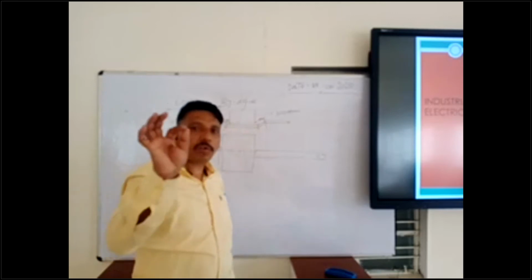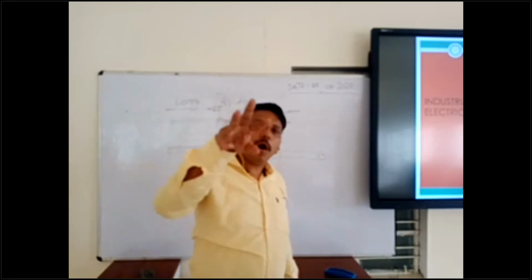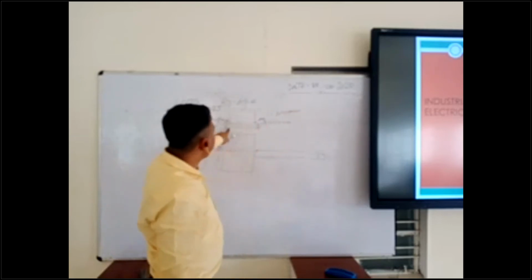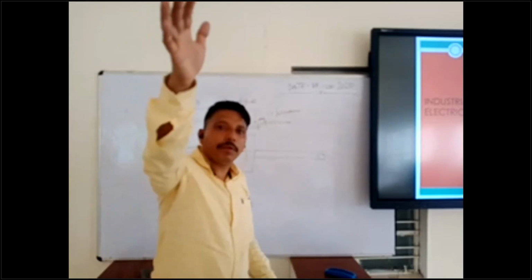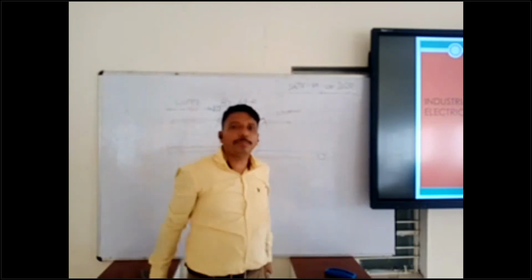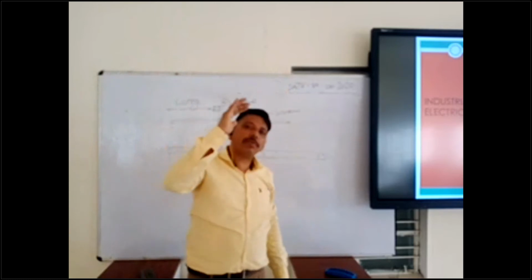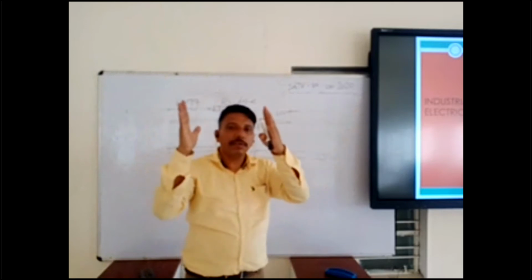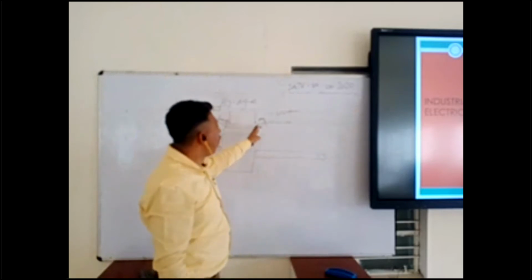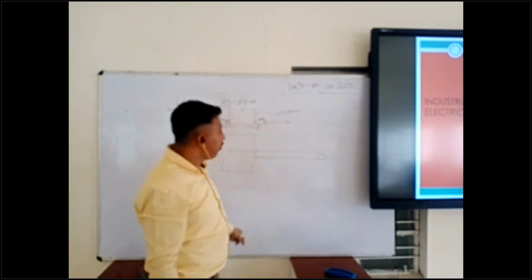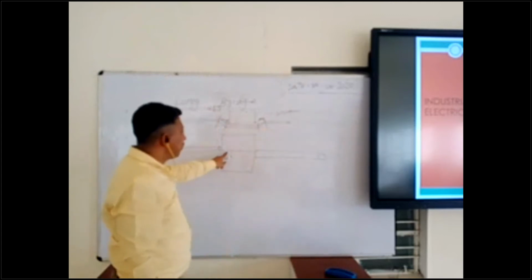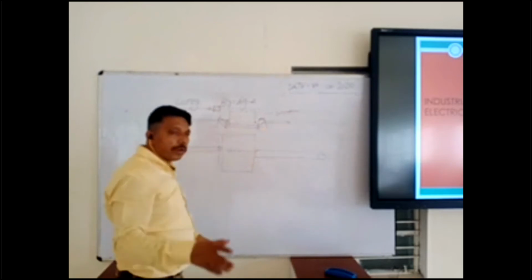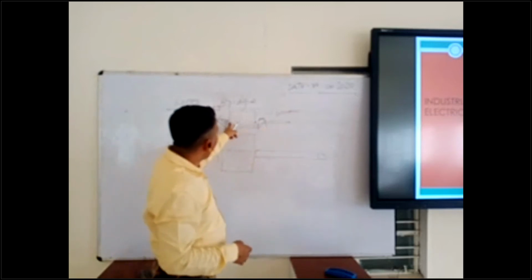So a small bend is used if you are crossing around 1 pipe or 2 small pipes. And a long bridge is used for crossing a beam or other objects with a distance of around 20 centimeters or above. That time we use the long type bridge. So this is the long type bridge, and I will give 2 examples for you. Don't forget this one.